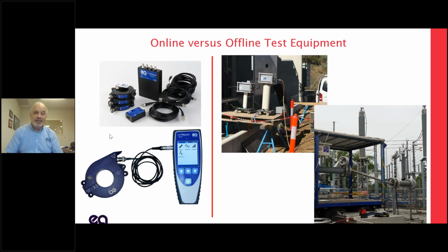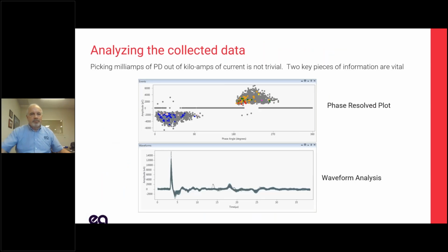It's not as effective as offline testing. So maybe you've got 100 cables, again, like my old example. I test 100 cables. I find out that 5 of them are showing something, and maybe I do an offline test of those 5, or maybe I just plan on one of those 5 failing. So it's a balance, but scanning a lot of cables with online test equipment can be very helpful.